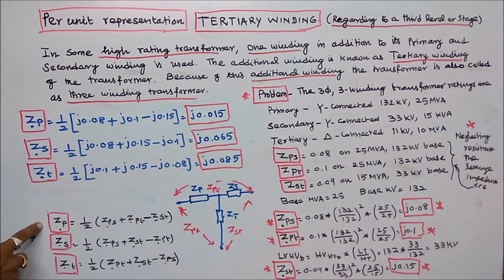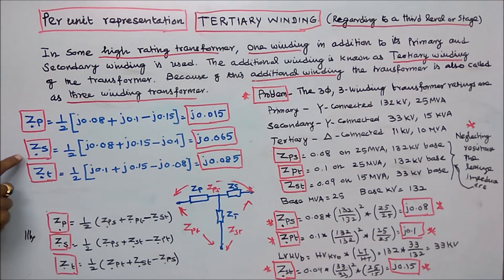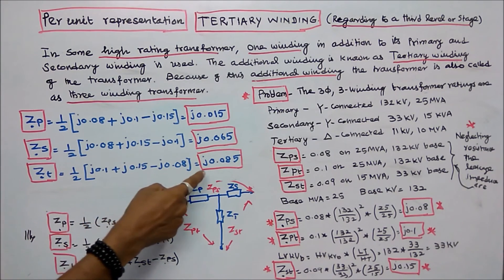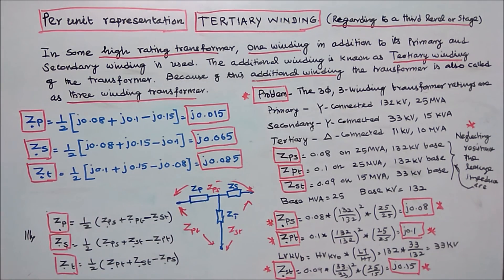By applying the formulas for individual winding impedances, the per unit impedance of primary is j0.015, the per unit impedance of secondary is j0.065, and the per unit impedance of tertiary winding is j0.085. With this, I conclude my lecture. Thanks for listening.